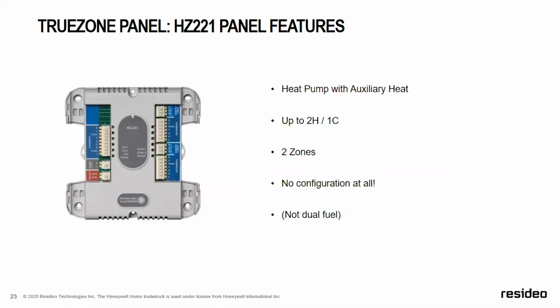You still do want to use a discharge air temperature switch. It does not do dual fuel. So if you have propane, gas-fired furnace, this will not work with that. Again, this one is not configurable. It defaults at high temperature of 160, low temperature of 40.